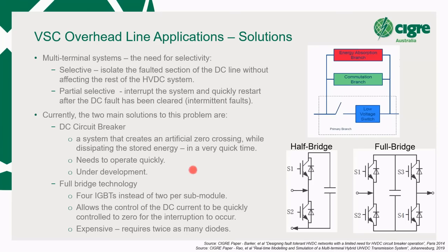Now, the full bridge, the difference is shown here. Effectively, it's a way of switching that you can control the DC fault current to zero by reversing the DC voltages momentarily across the converter arms. And you can only do that with the flexibility that a full bridge switching configuration provides. The disadvantage of full bridge is that you need twice as many IGBTs. And twice as many IGBTs means more losses.